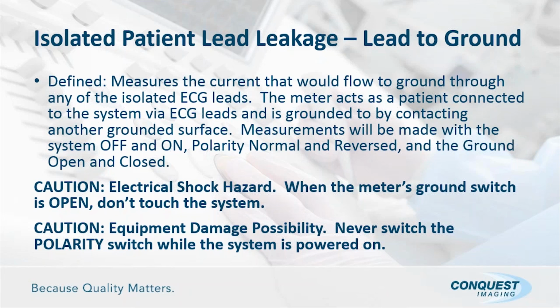Well, just to clarify that: the meter acts as a patient connected to the system via ECG leads and is grounded by contacting another grounded surface. As an example, if these leads were connected to a patient and the patient held on to the bed rail that was plugged into the wall and had its own ground, well, there's the simulation of what this is basically acting as.